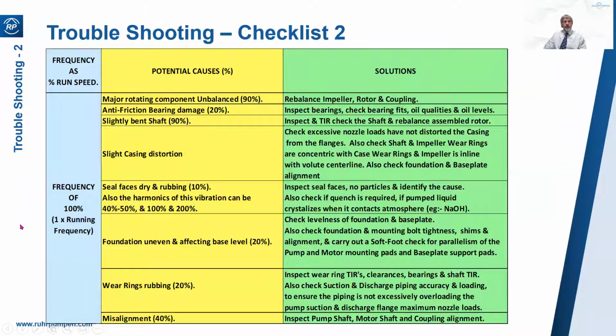This one is interesting. These are peaks at 100% running speed. Note that 90% of the time, it's a rotor unbalance or a bent shaft. And 40% of the time, it's misalignment. So again, this is the easy thing to check: the pump, motor shaft, and coupling alignment. And if you've still got a vibration after that, take the pump out and check the rotor.